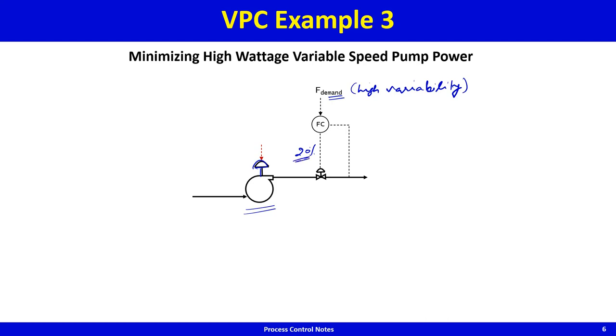If the valve is only 20% open, it is highly pinched, meaning the pressure differential across it is high. This means the pump is being run at an unnecessarily high RPM to raise the pressure, only to then drop most of that pressure across the valve. The fact that the valve is not nearly fully open indicates the pump is running at an unduly high RPM.